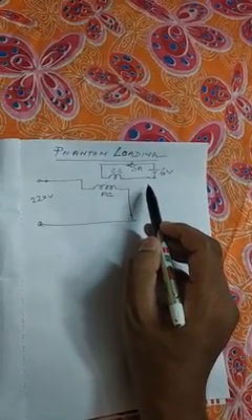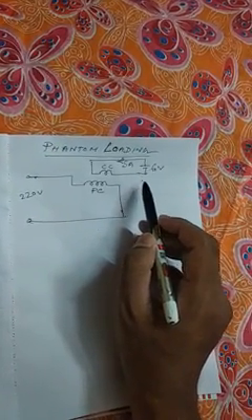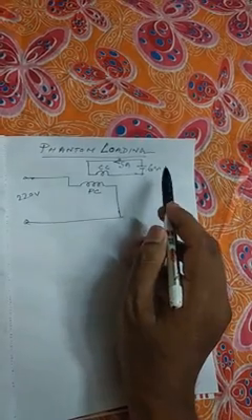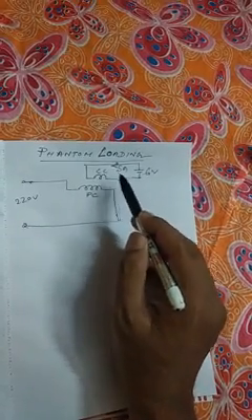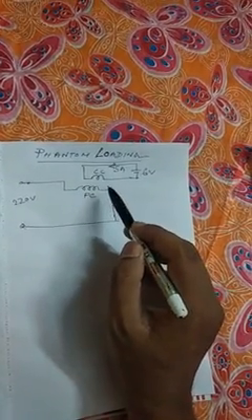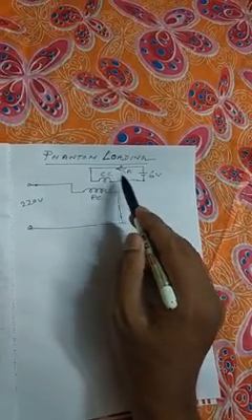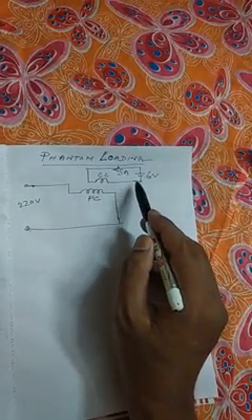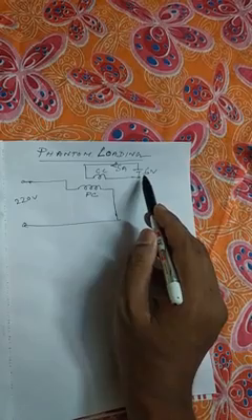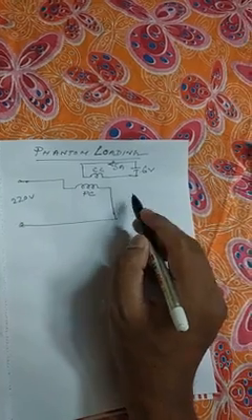So unlike the conventional way, no output loading will be there. Without the output loading, we are getting the energy consumed by this energy meter by internally connecting a 6 volt supply. That's why this technique is called the phantom loading technique.